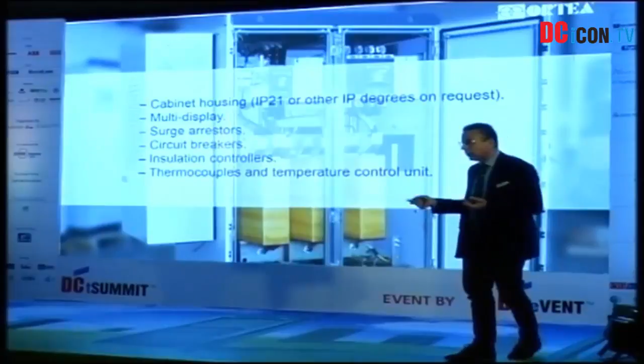So these are some accessories and specific configuration. Here you can see in the photo a transformer fitted in an IP54 cabinet with air conditioning system and breakers. So this was under request from one customer for a specific application. Normal transformer, isolation transformer, different power. Line transformer, so for nonlinear loads, different K rating. Mostly in data centers you use K20 rating.